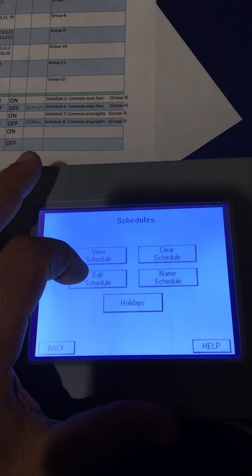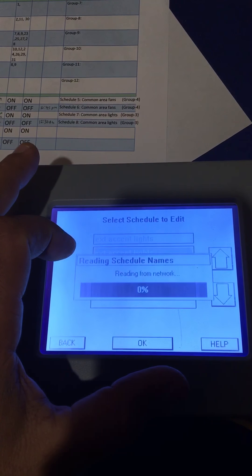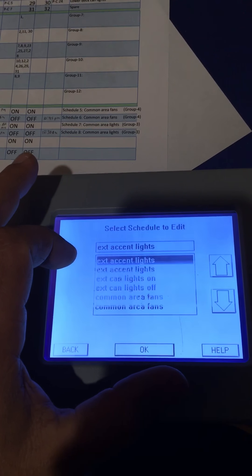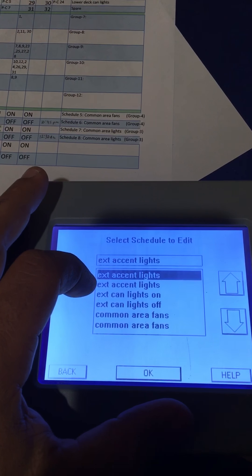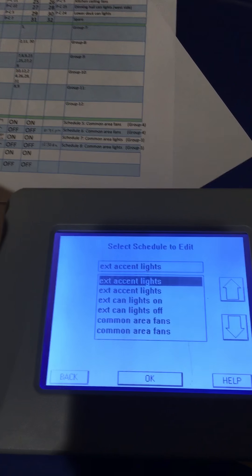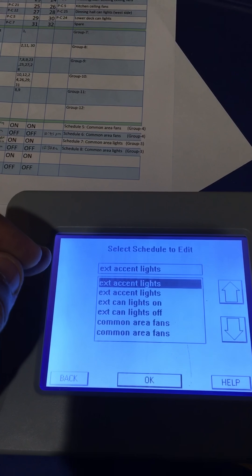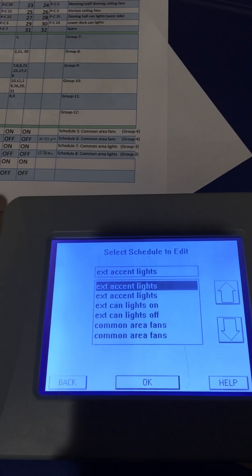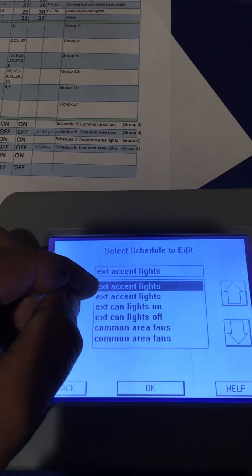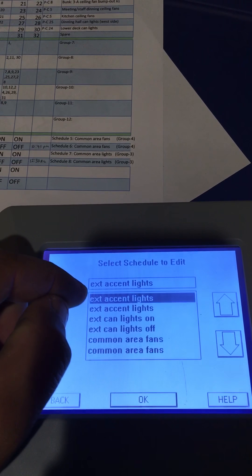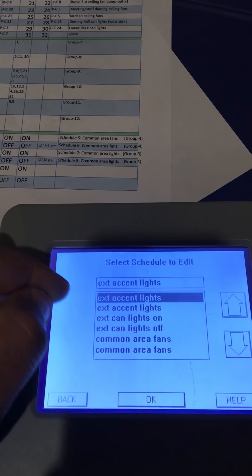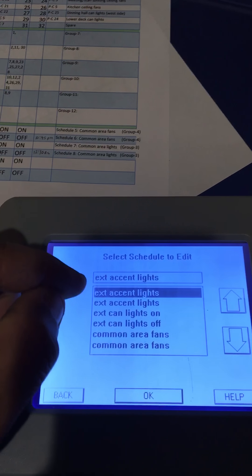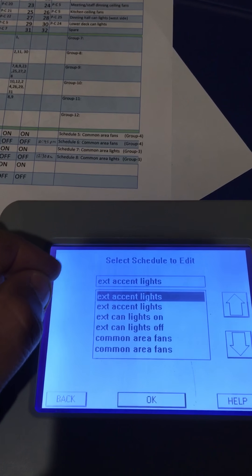We are going to edit schedule. A schedule is just like a toggle switch - you have on and off. You cannot control both on and off from schedule 1. Schedule 1 can only control on, and then schedule 2 is for the same group of relays but turning them off.